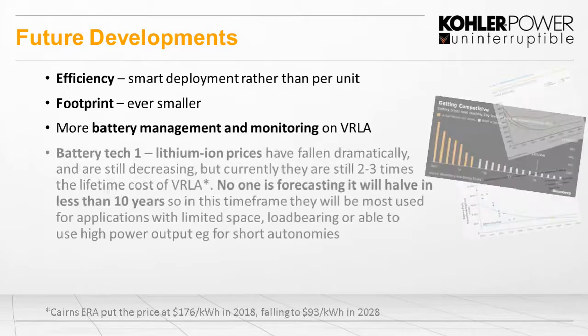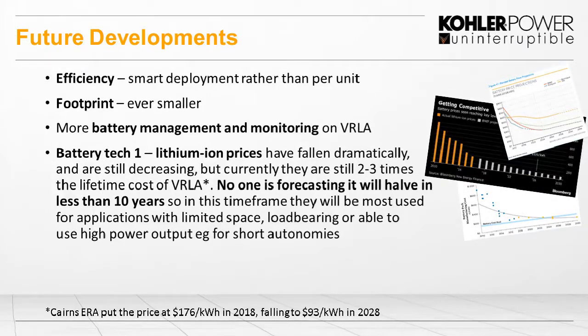But talking about batteries, obviously a lot of people hear about lithium batteries. The prices have fallen quite dramatically in recent years, but they are still typically, for UPS situations, 2 to 3 times the cost of a typical lead acid, and we're not seeing that dropping to half that in the next 10 years or so. There are limited uses of lithium, especially as they are very light. So in some situations, lithium technology can definitely be an answer, especially around short autonomies, where lithium has some advantages.